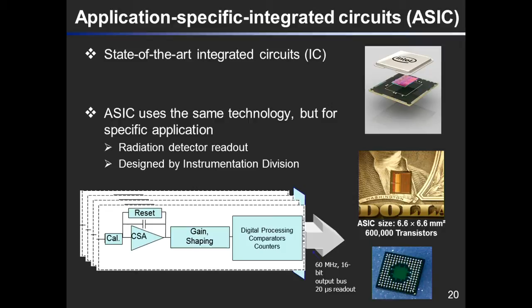Now we have the key component in our hands, we can build the system. What we did is we made a printed circuit board. Then we attached the CdTe detectors on top of the board. On the bottom side of the board, we attach our ASIC. Beside that, we also have a readout control logic, which is simply a microprocessor. We can read out signals from the ASIC, then communicate with the computer. This is a photo of a real detector module we built for our application. This is one side of the printed circuit board. You can see two CdTe detectors. The total area is about 15 by 40 millimeter square.